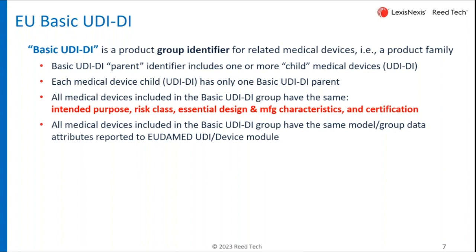But it can have multiples — it can have 20, 50, 100, or technically 1,000 different devices, all part of that particular Basic UDI-DI group. Now, for every individual device, it has to have one and only one parent, so you can't have a particular device sitting in two different groups.